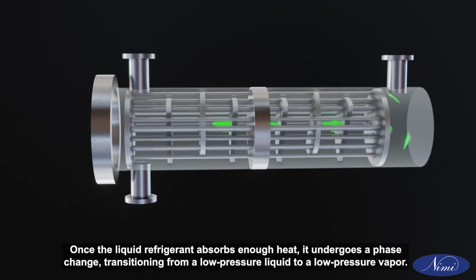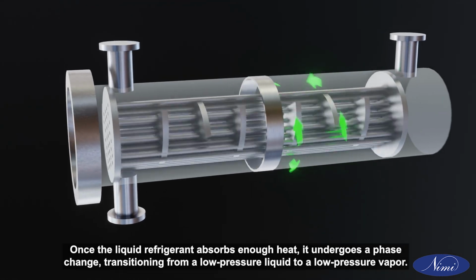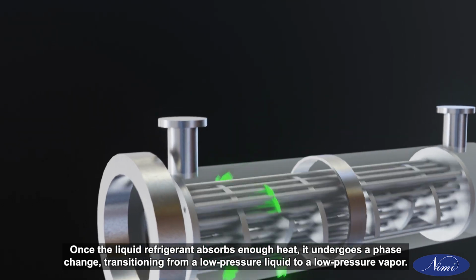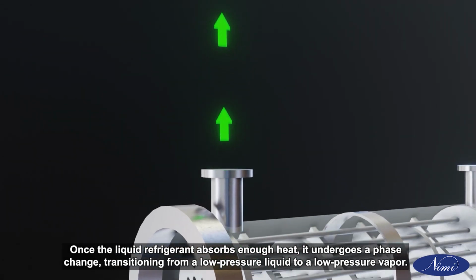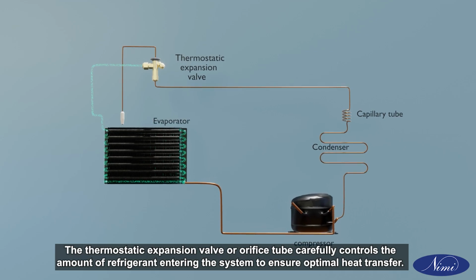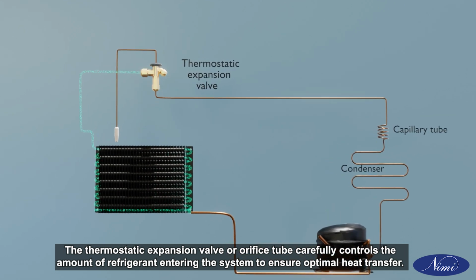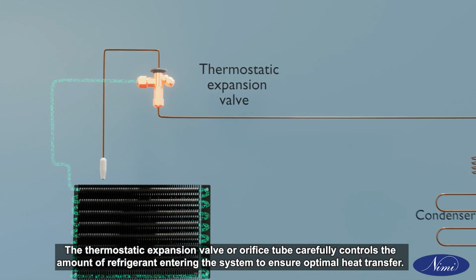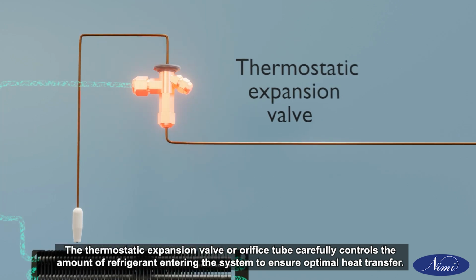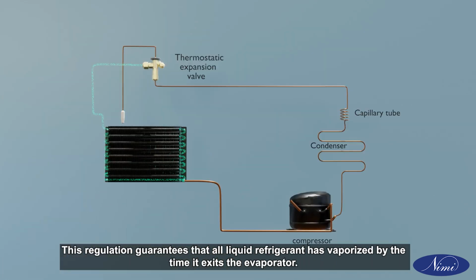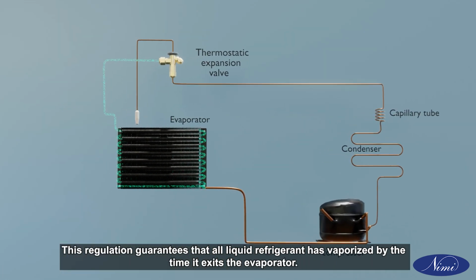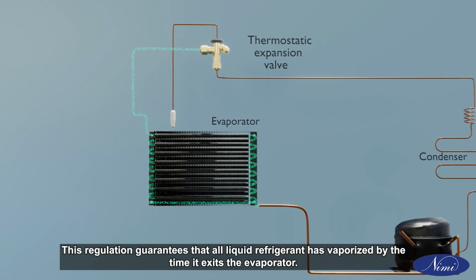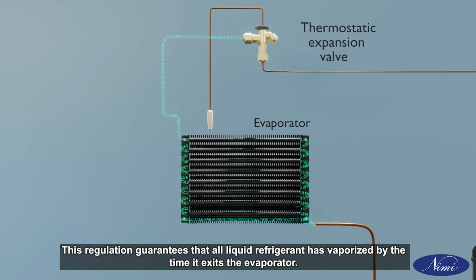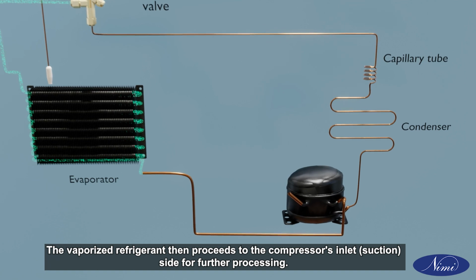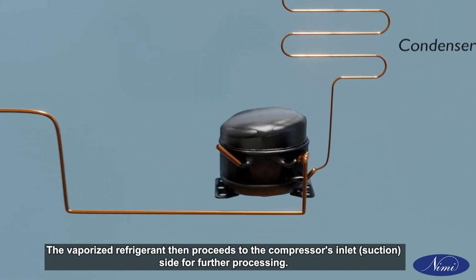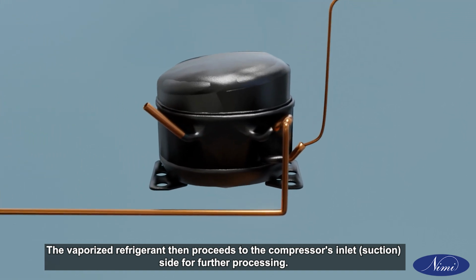Once the liquid refrigerant absorbs enough heat, it undergoes a phase change, transitioning from a low-pressure liquid to a low-pressure vapor. The thermostatic expansion valve or orifice tube carefully controls the amount of refrigerant entering the system to ensure optimal heat transfer. This regulation guarantees that all liquid refrigerant has vaporized by the time it exits the evaporator. The vaporized refrigerant then proceeds to the compressor's inlet, suction, side for further processing.